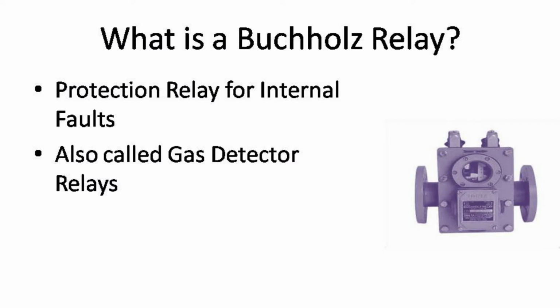So now let's step back a bit. What is actually the Buchholz relay? Well, the Buchholz relay is installed particularly in oil-type power transformers and is used as a protection relay for internal faults. It's also known as the gas detector relay.